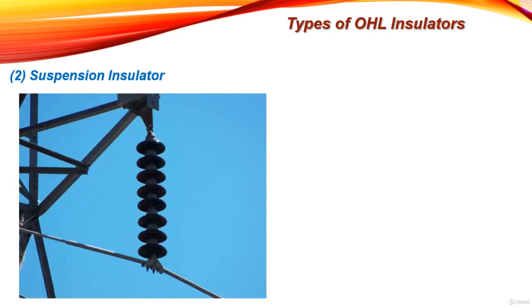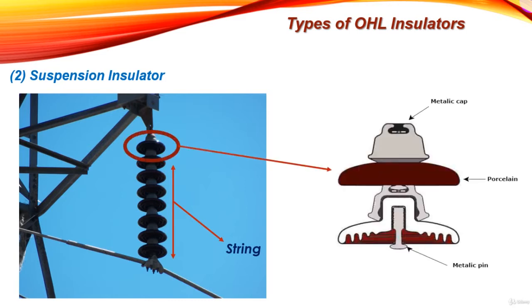For higher voltages above 33 kilovolts, it is usual practice to use a suspension type insulator. It consists of porcelain disc units mounted one above the other to form an insulator string. The insulator string consists of many such units, each unit referred to as a disc unit, and many units together form a string.